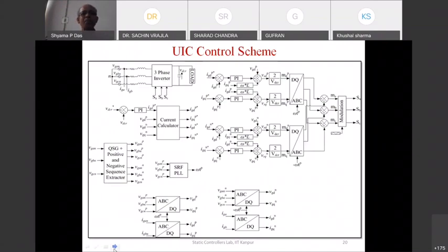It means if the DC link voltage comes down, the DC link is depleted of active power, and active power has to be brought from the grid. So IGD has to be increased. Active power is only increased by increasing IGD, and reduced by reducing IGD, because IGD is the only current that involves active power.